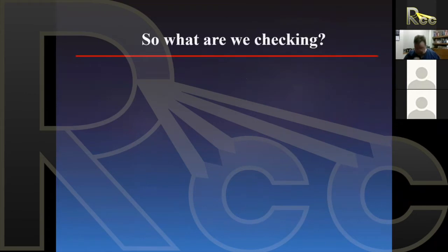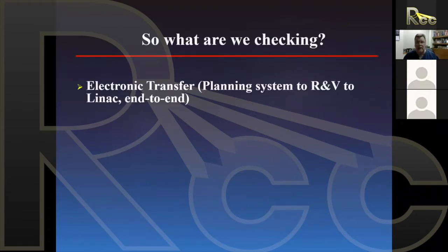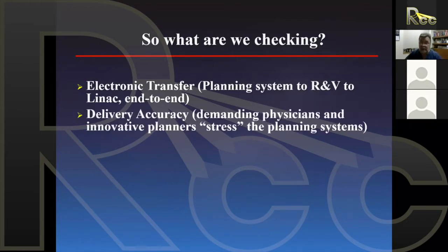So what are we checking? We're checking the electronic transfer, from the planning system, to the record and verify system, to the LINAC. This is a true end-to-end test of delivery once we have an acceptable plan. The delivery accuracy. We have very demanding physicians and we have very innovative planners and they stress the system.